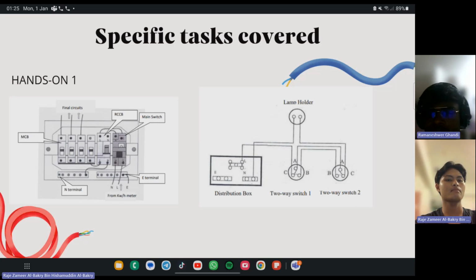The picture next to it is a schematic diagram of a lamp circuit. In the lamp circuit, the two-way switches are connected to the live terminal of the distribution board, then connected to the lamp holders, and the lamp holders are connected to the neutral terminal of the distribution board. So how is this lamp circuit installed?